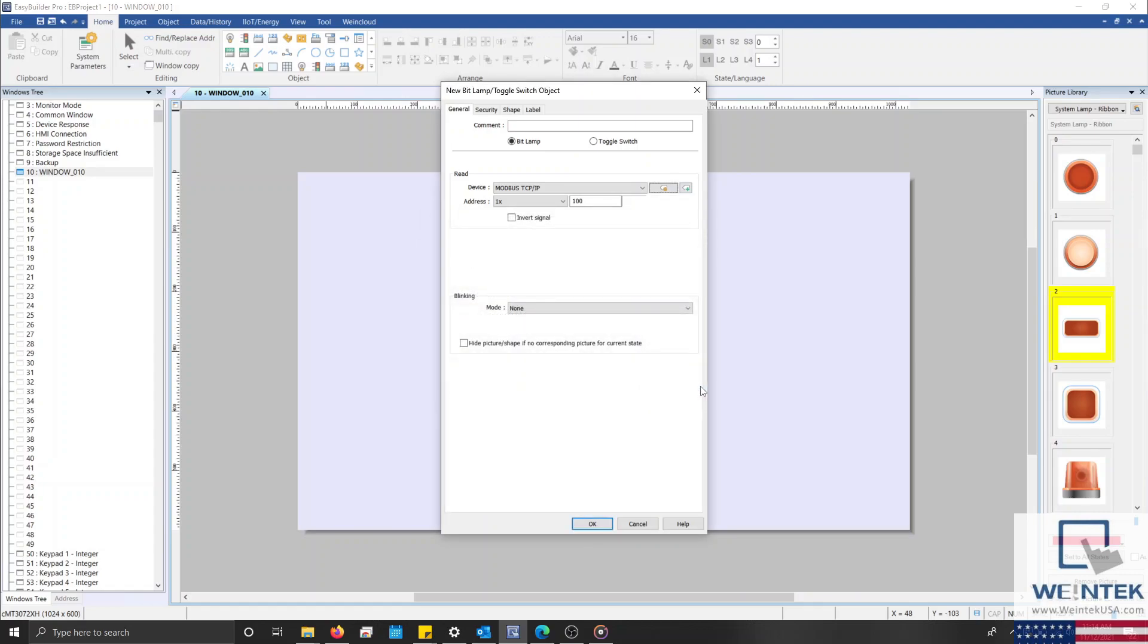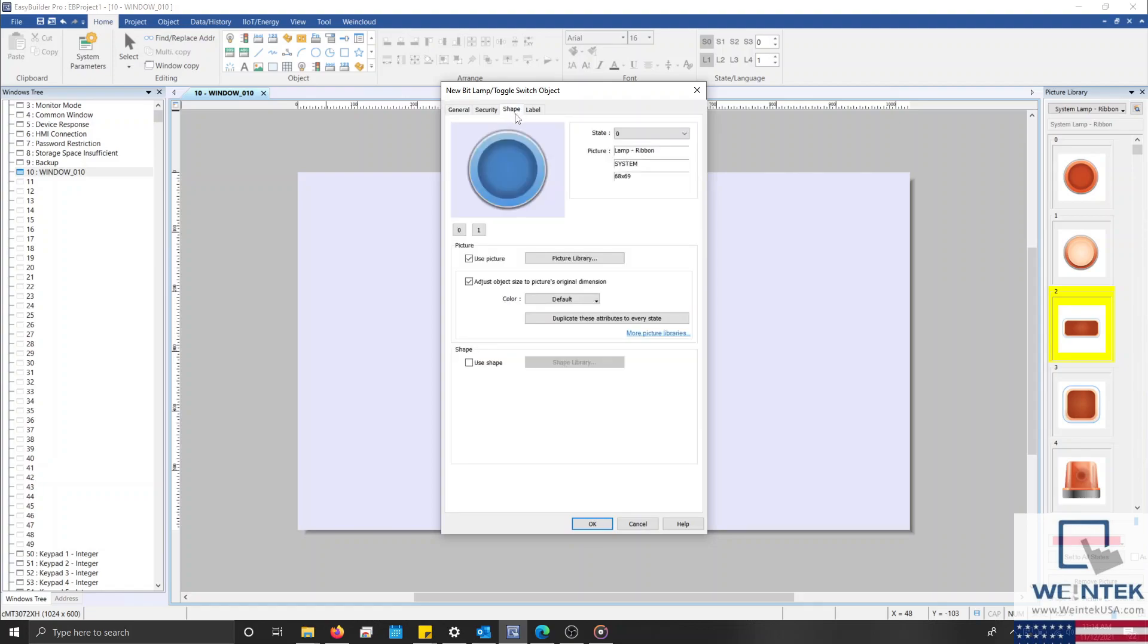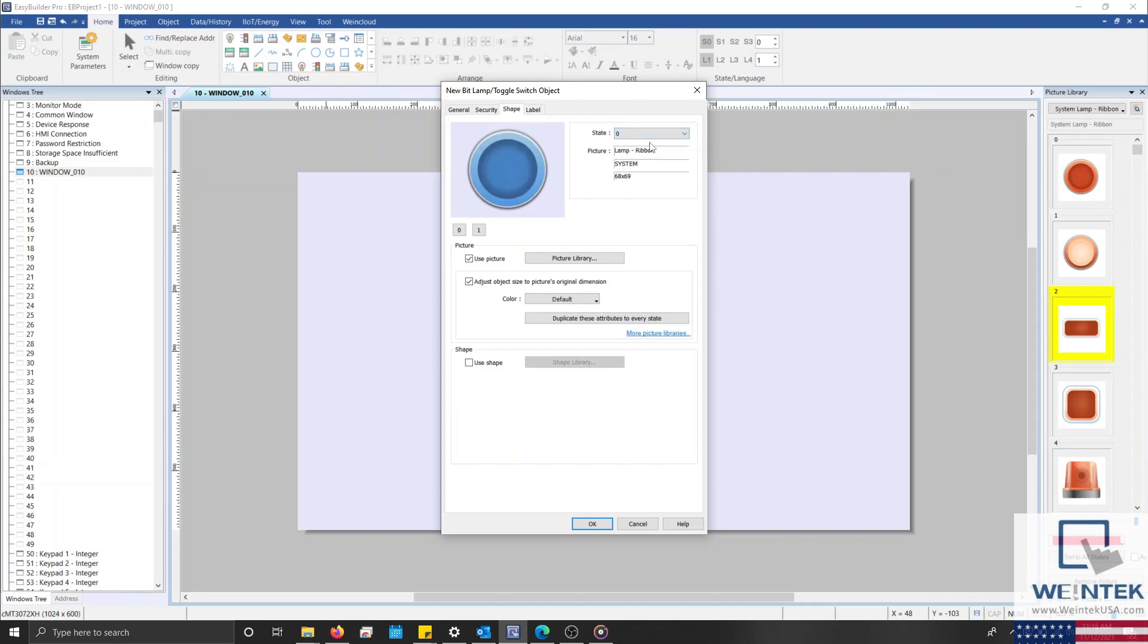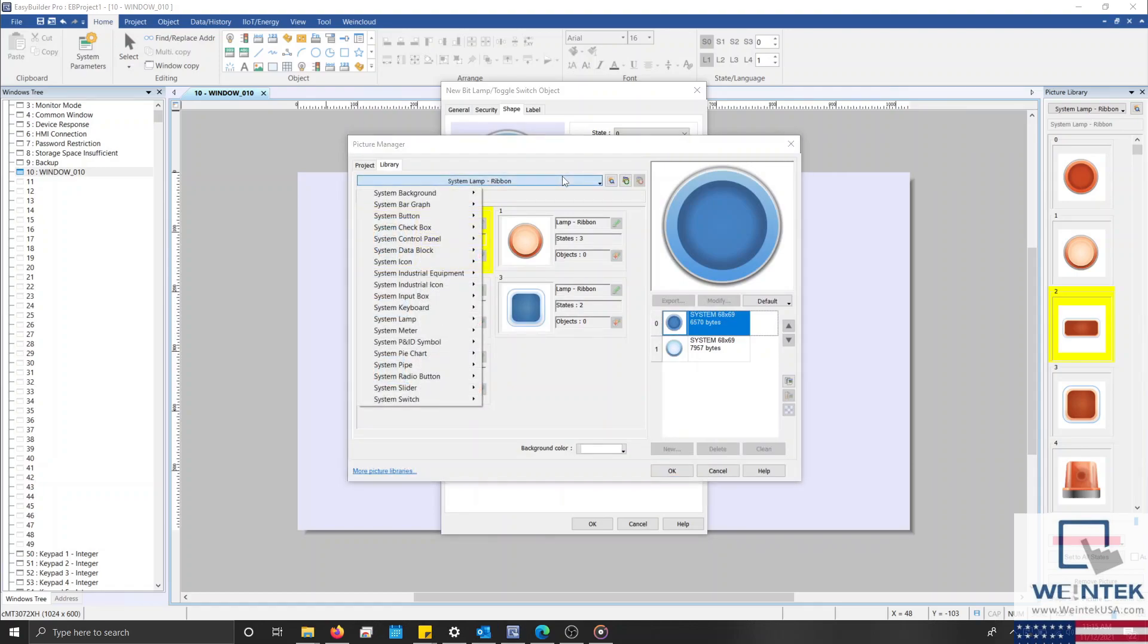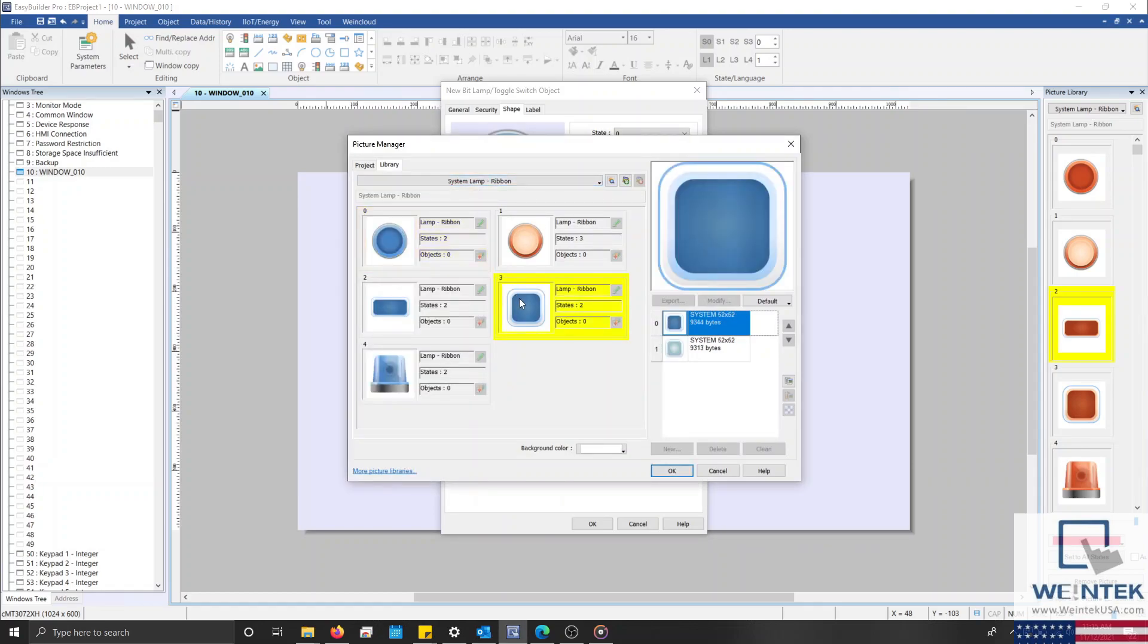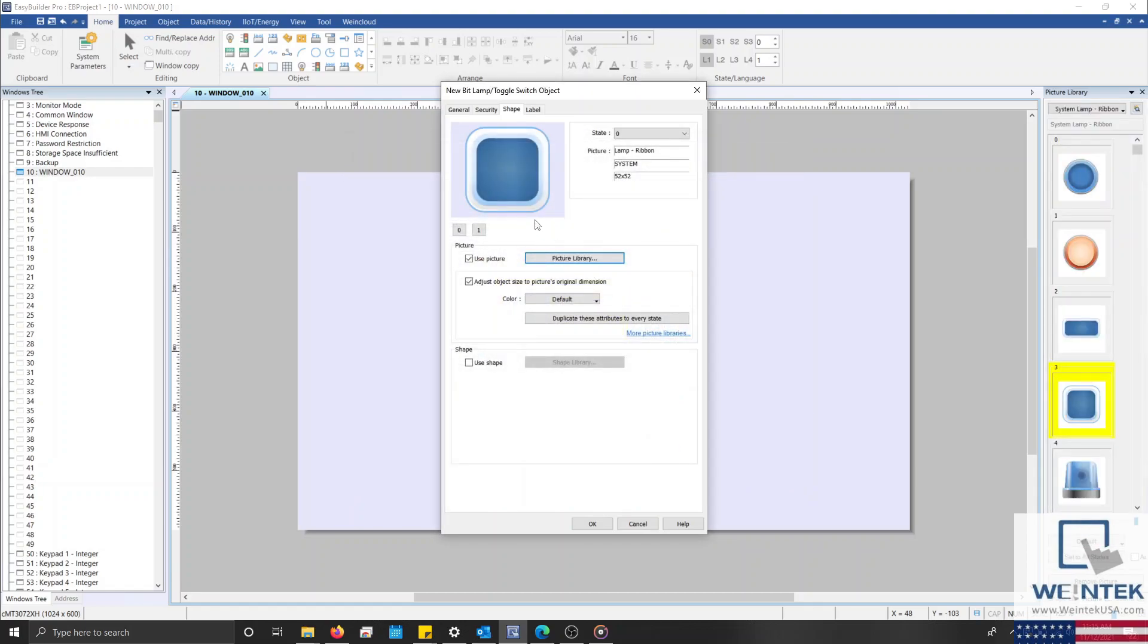Now that we've configured the address of our bitlamp, let's define the shape or picture that our bitlamp will display. To do this, we'll select the Shape tab, where at the top we can select the State drop-down list to view the image associated with each state. We can also preview a limited number of states by selecting the numeric icons shown below the preview. While Use Picture is selected, we can choose a system or custom image from our extensive picture library. Once we find or design an appropriate image, we'll select it and then click OK to close our library, and the preview shown will reflect our new image.